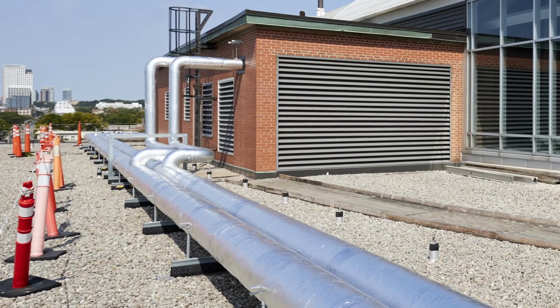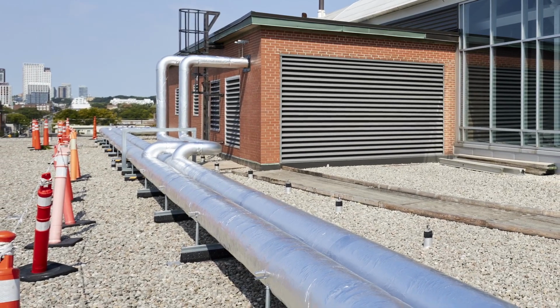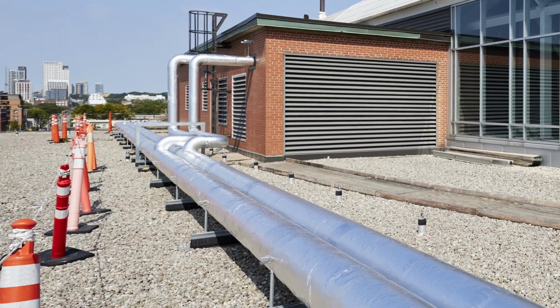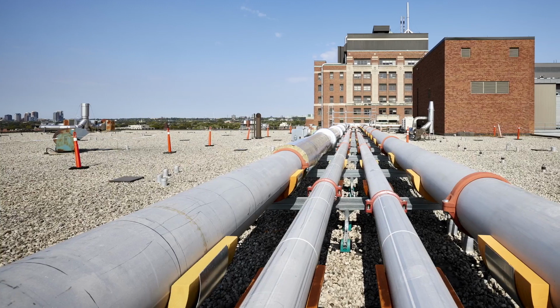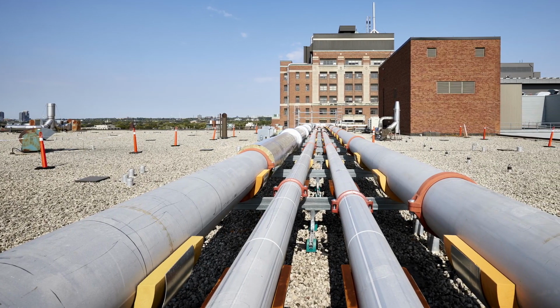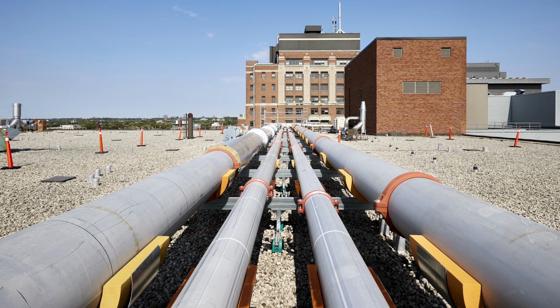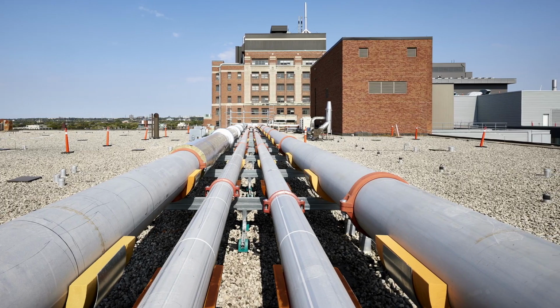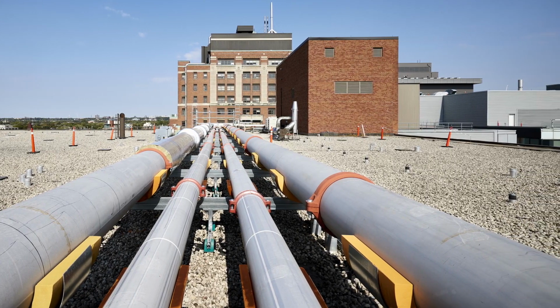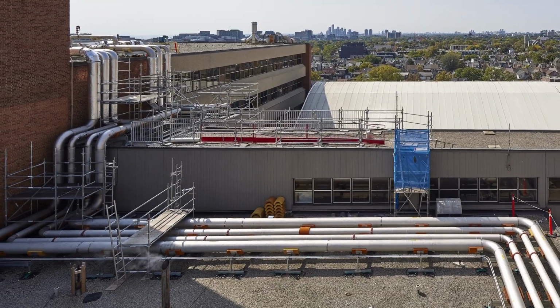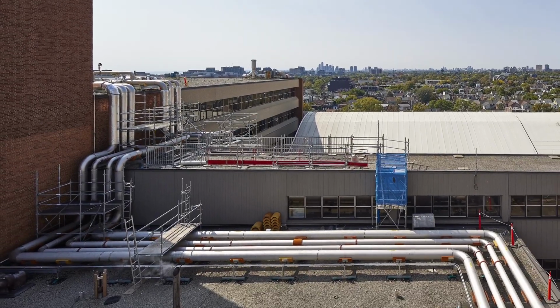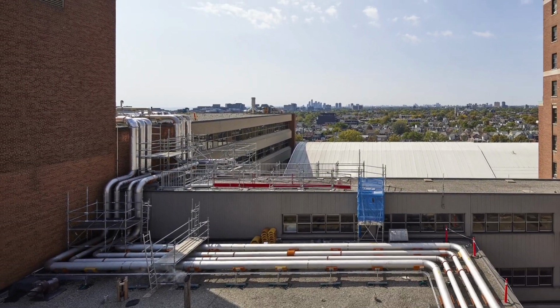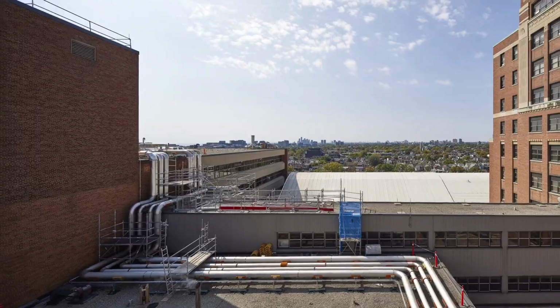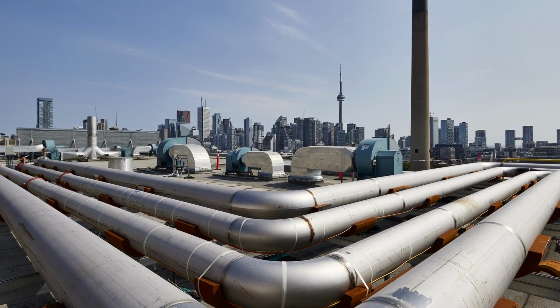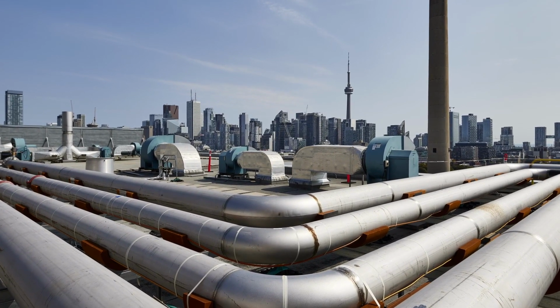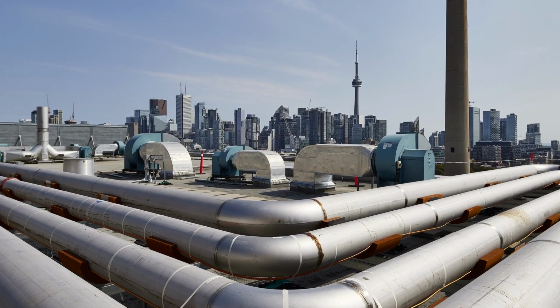All major plant equipment will have an N+1 redundancy and enough generator capacity to island the facility to avoid the global adjustment charges, providing substantial operational cost savings. The new low temperature heating system will additionally require the replacement of the air handling unit coils across the hospital. On top of the new hydronic piping system, the project also includes the construction of a new central utilities plant with waste-to-energy heat exchangers, heat pumps, heat exchangers, and pumps.